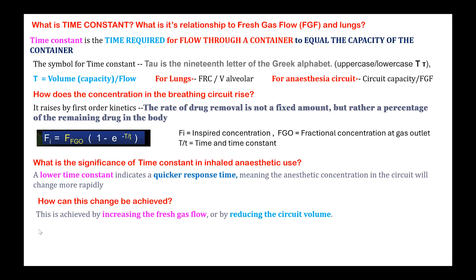So how can this change be achieved to get a quicker response? One is increasing the fresh gas flow, or reducing the volume of the circuit. So you remove unnecessary components like extra connectors or reduce the volume of the tubing, then you will be able to achieve a faster response time and induce the patient much faster.